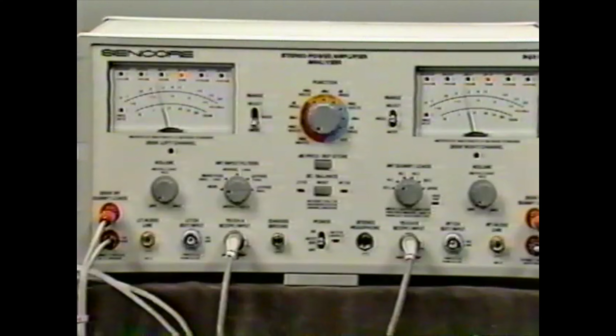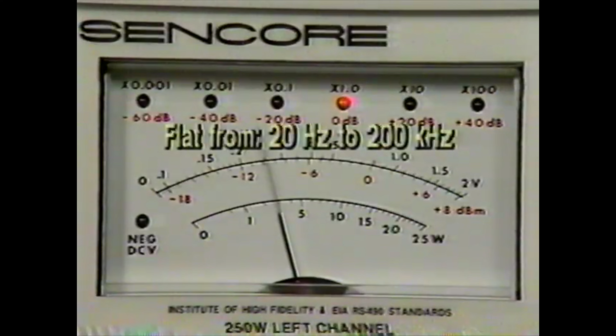The SG165 was pretty handy. It easily let you measure 30 decibels, 40 with some estimating. The PA81 does much better. It measures all the way to 126 decibels. What's more, you may not have realized that the SG165 meters were only accurate at the 400 hertz frequency supplied by its internal generators. The PA81 meters are flat from 20 hertz to 200 kilohertz.